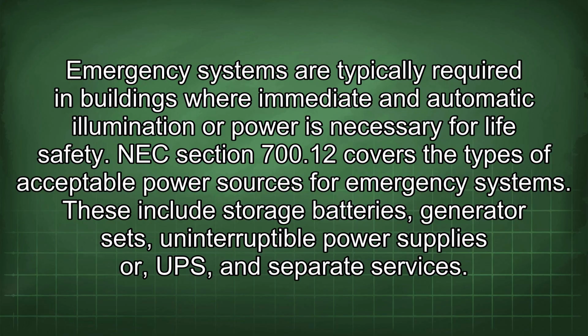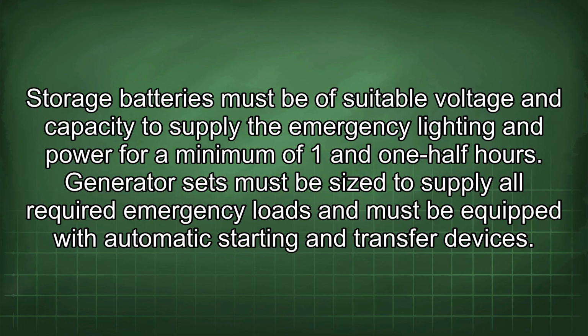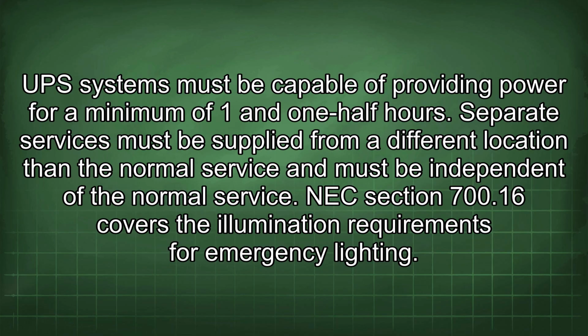NEC Section 700.12 covers the types of acceptable power sources for emergency systems. These include storage batteries, generator sets, uninterruptible power supplies or UPS, and separate services. Storage batteries must be of suitable voltage and capacity to supply the emergency lighting and power for a minimum of 1.5 hours. Generator sets must be sized to supply all required emergency loads and must be equipped with automatic starting and transfer devices. UPS systems must be capable of providing power for a minimum of 1.5 hours. Separate services must be supplied from a different location than the normal service and must be independent of the normal service.